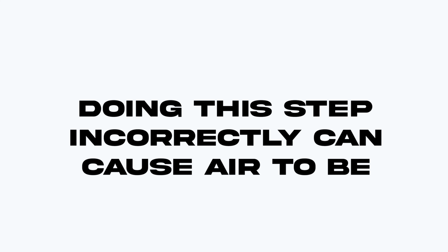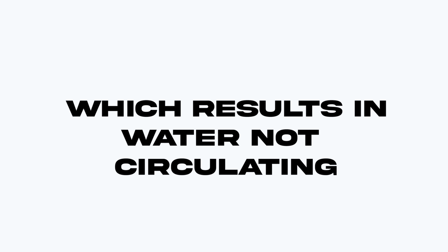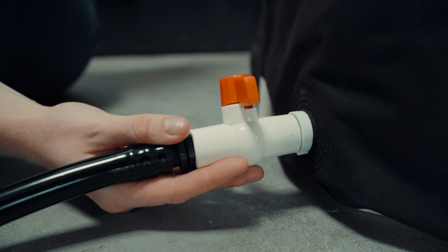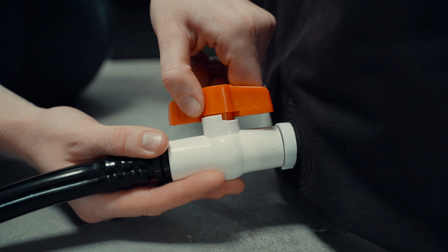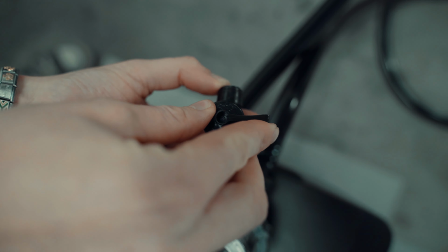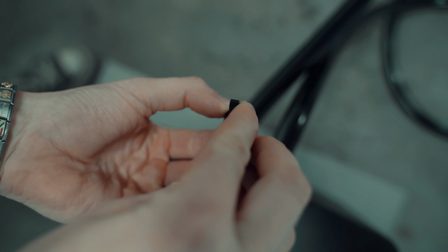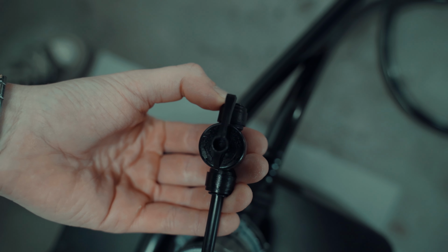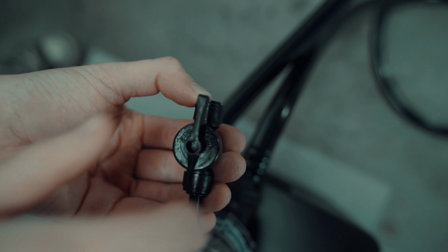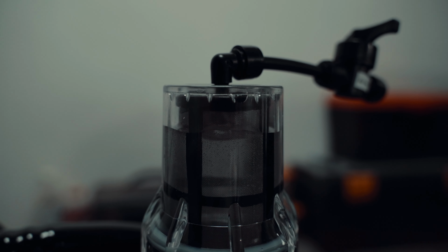Step 7. Let water into the chiller and vent excess air. Please pay extra attention to this step. Doing this step incorrectly can cause air to be trapped inside the system, which results in water not circulating into the ice pod. Open the bottom ice pod valve that connects via hose to the filter. Next, open the smaller air release valve on the filter, which will release excess air, so the water can flow into the chiller. Close the filter valve once the filter's full of water and water's running out at the top.